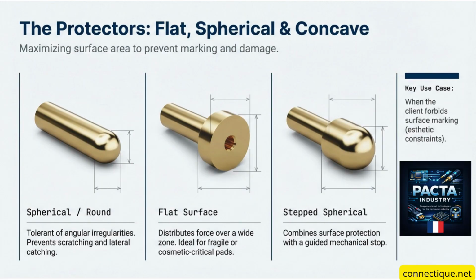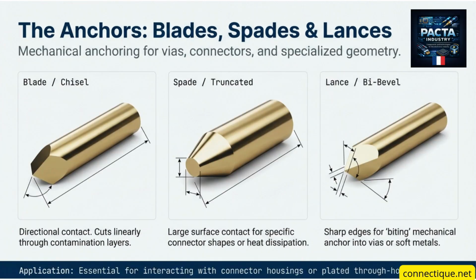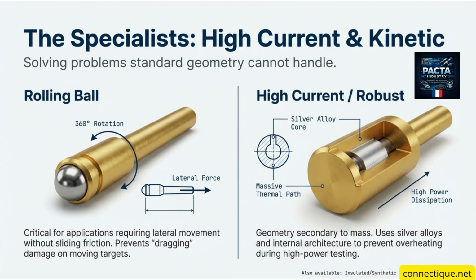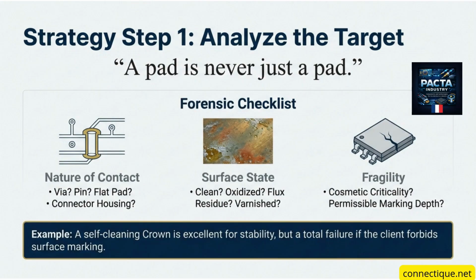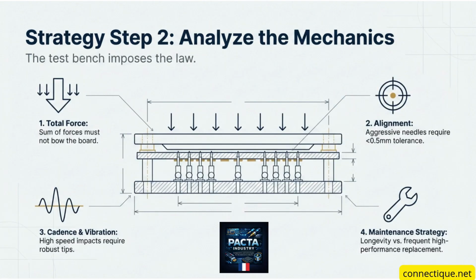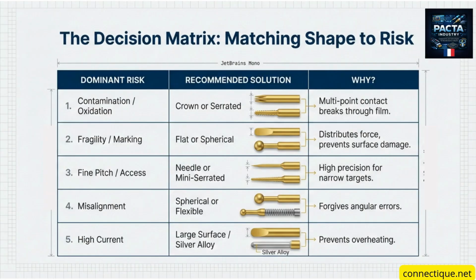Okay, so that's the stabbing approach. Right. But what if we can't stab? What if the customer says, no marks allowed? Right. The source lists flat and spherical tips. Styles 11, 12, 17. Now we enter the gentle touch category. You have to think about something called the plowing effect. Plowing, like on a farm. Similar idea. If you have a sharp tip and the alignment isn't perfect, the probe comes down a little sideways, it drags across the metal as it compresses. It digs a trench. Digs a trench.